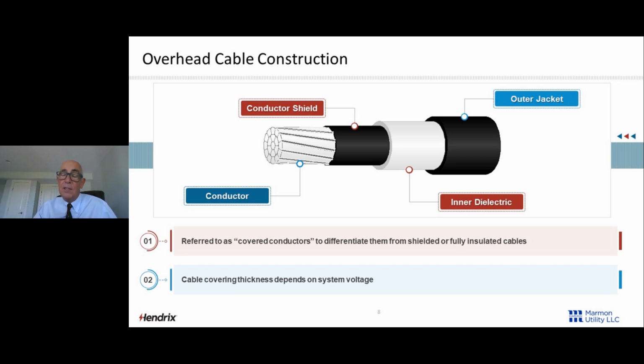That outer jacket, high-density polyethylene, is also where we put the track-resistant additive. We don't want to have tracking. It's also where we put the UV inhibitor. And that UV inhibitor is a chemical UV inhibitor. It's not fugitive. It will not leak. It puts a chemical umbrella over the molecular chains and protects them from UV rays. And lastly, it's where we put the color. We have black, we have gray, and it depends. There's arguments for black and gray. Usually for the higher sizes and the higher voltages, we use gray because we don't want to have ampacity derating, if you will.